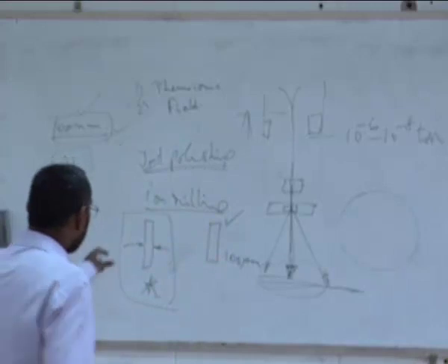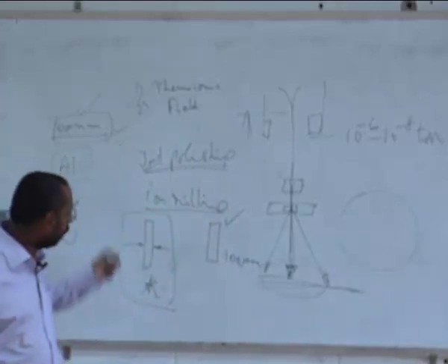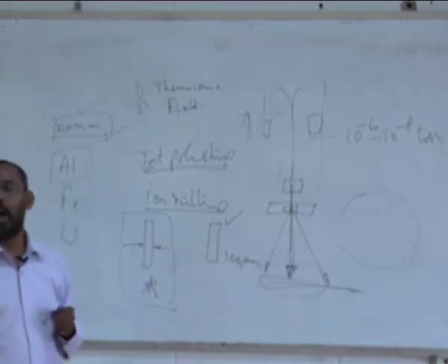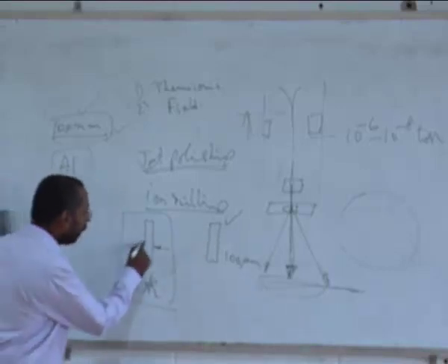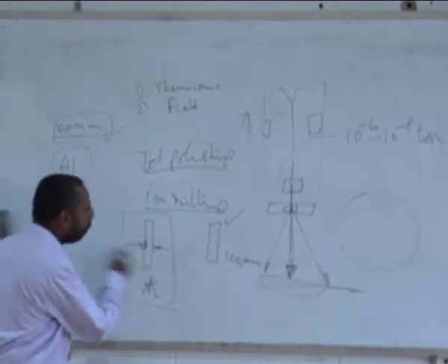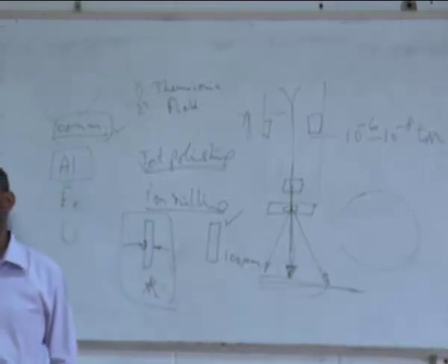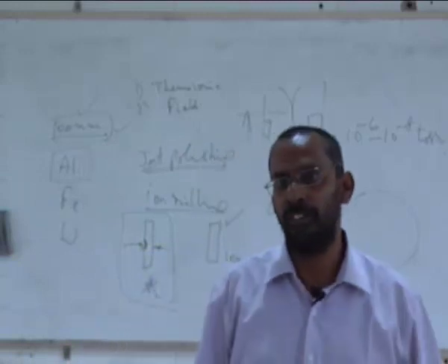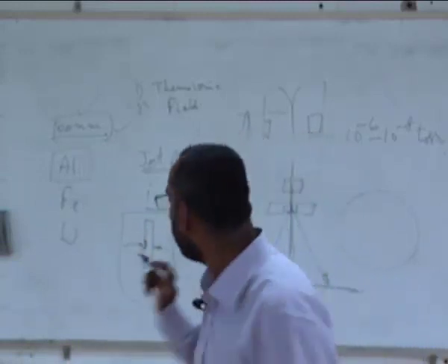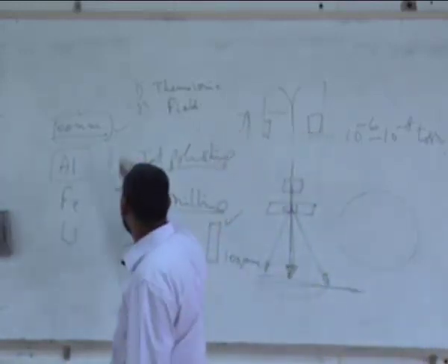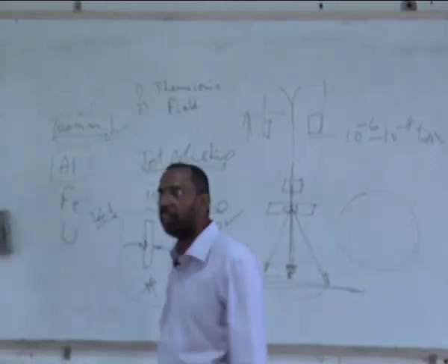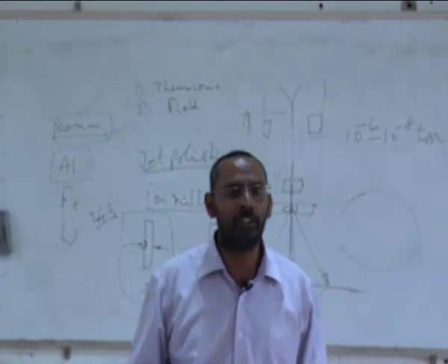So this particular thing we do by bombarding an ion beam onto the sample so that atom by atom are removed, sputtered away. Obviously, because this is happening atom by atom, it is a very slow process. For example, a sample from 100 microns to go to 100 nanometers might take about 24 hours. Whereas jet polishing is just about a 2 or 3 minutes job.